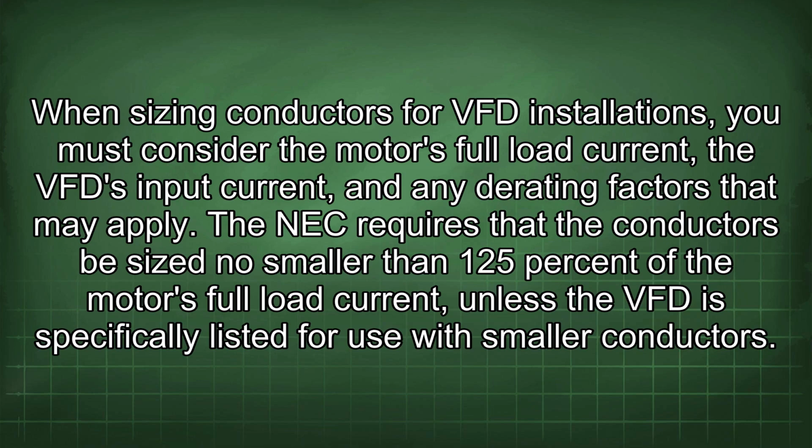When sizing conductors for VFD installations, you must consider the motor's full load current, the VFD input current, and any derating factors that may apply. The NEC requires that the conductors be sized no smaller than 125% of the motor's full load current, unless the VFD is specifically listed for use with smaller conductors.